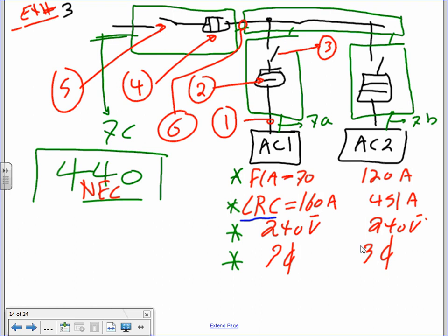Seven A is the equipment grounding conductor for unit one, seven B for unit two, and seven C the equipment grounding conductor for the whole system. We need to size these seven things. You could have 30 chillers and it would be the same calculation. The reason I picked two is because after two, you add a third and the sizes just get bigger — the calculation doesn't change.